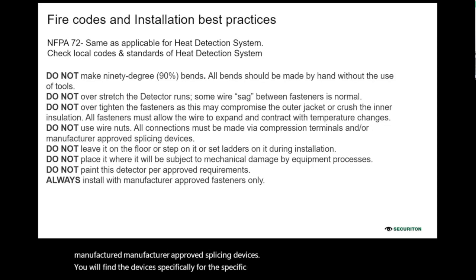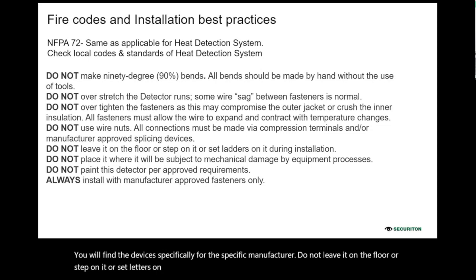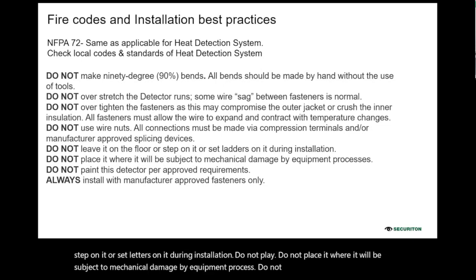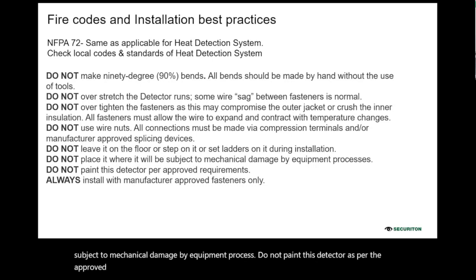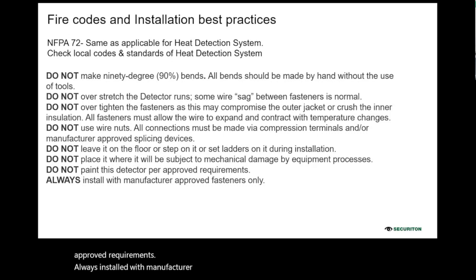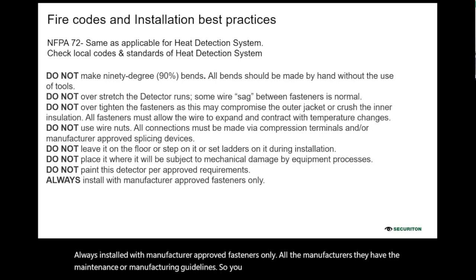Do not leave it on the floor or step on it or set ladders on it during installation. Do not place it where it will be subject to mechanical damage by equipment processing. Do not paint this detector, as per the approved requirements. Always install with manufacturer approved fasteners only. All the manufacturers have maintenance or manufacturing guidelines, so you should follow these kinds of guidelines.